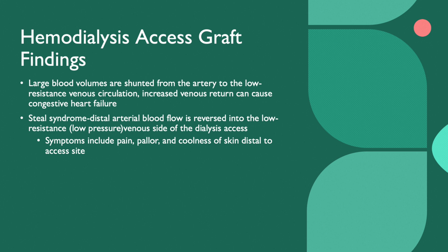So a lot of these patients will take the arterial machine and use those little PPG photo sensors to check for pulses in the finger to indicate, okay, is this fistula stealing too much blood from the hand? Because that's a problem. They'll have to go in and fix that.